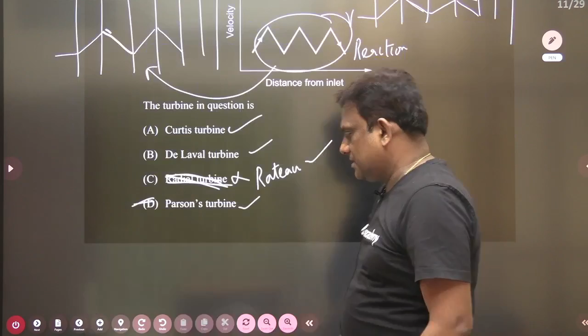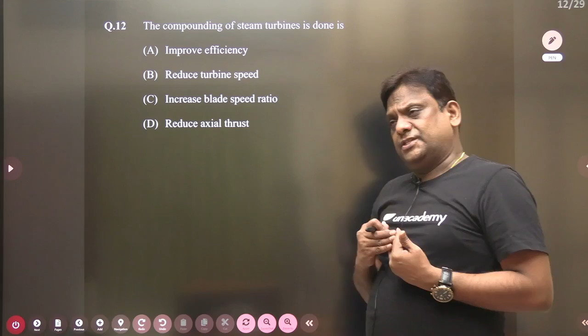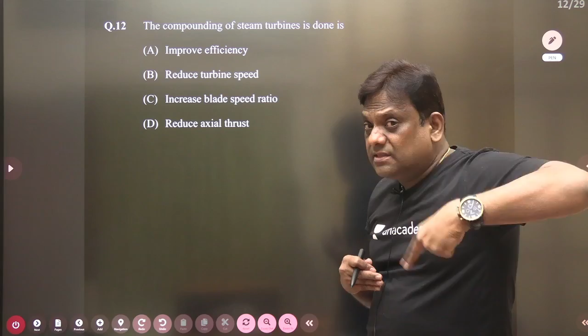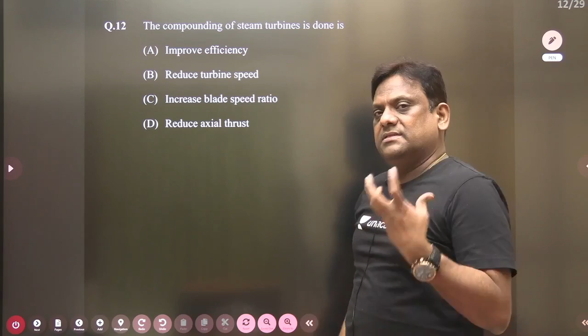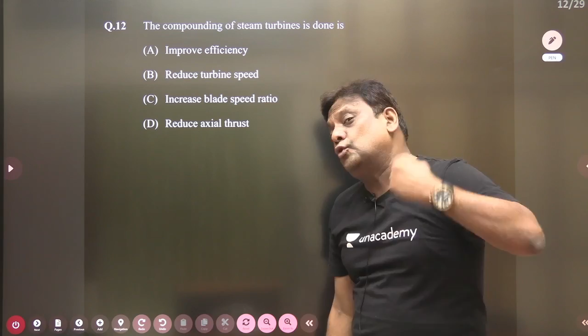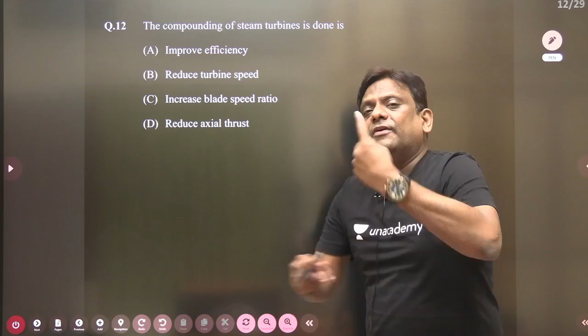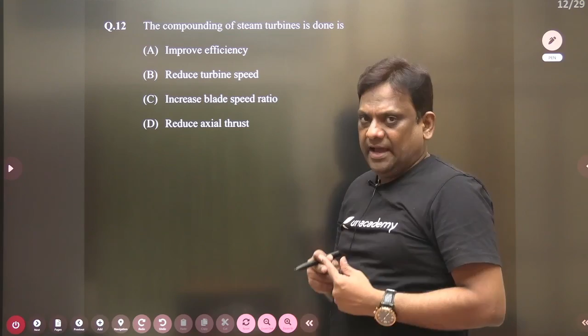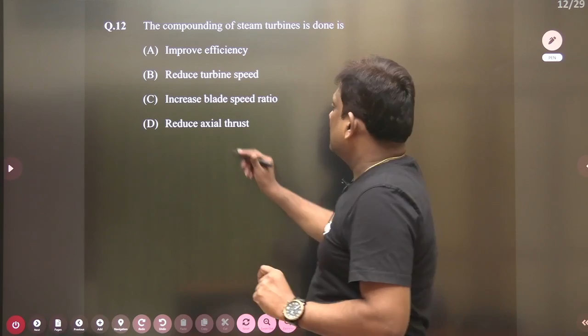And compounding of steam turbines is done. I explained very clearly. In case of steam turbines, if it is a high pressure boiler, the boiler pressure is greater than 80, maybe 100, 150, 180. If it is a supercritical boiler, above 220, 221.2, maybe 250 bar also. And the condenser pressure is very much less than atmospheric. The ratio of boiler to condenser pressure is very high, unlike gas turbines, where pressure ratios are about 10, 12. But here, it can even touch 4,000. If all is expanded in a single turbine with such a huge ratio, the rotor speed will be very high. Therefore, compounding is done to reduce the rotor speed. So therefore, this is the answer.